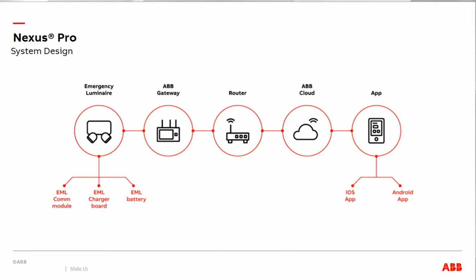To make sure the battery is fully functional and able to meet the discharge times Ron mentioned, either a 30-second monthly test or a 90-minute annual test, we have a charger board incorporated into the fixture. This periodically makes sure the battery is topped up and ready to function in an emergency situation.